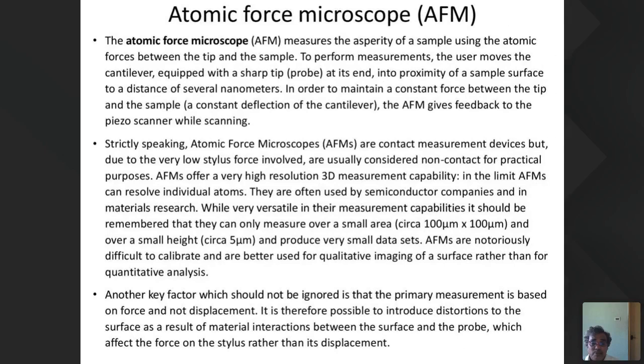The next important thing is the atomic force microscope. The atomic force microscope measures the asperity of the sample by using the atomic forces between the tip and the sample. You know that there will be a repulsive force and an attractive force between the sample surface and the tip. To perform measurement, the user moves the cantilever. Actually, a cantilever beam will be there. When there is a change in the atomic force, the cantilever will oscillate, or will deflect. That is quantified to study the structure.